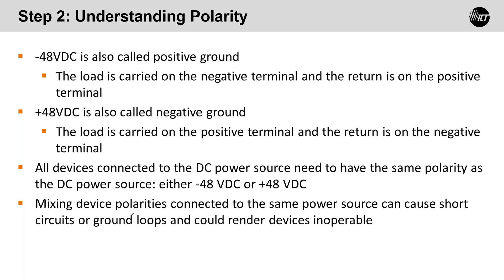Here's a wiring diagram, an example using our modular power series. This is what it would look like in a typical neg 48 system. When you see the battery, imagine there are 4 batteries connected in series to provide that 48 volt output. In this case, the load is on the negative side of the battery, wired into BAT minus, the minus terminal of the battery.